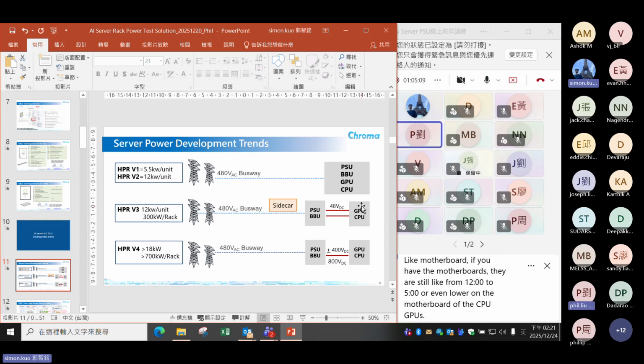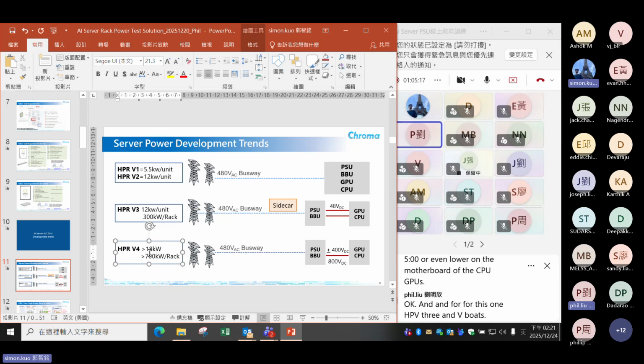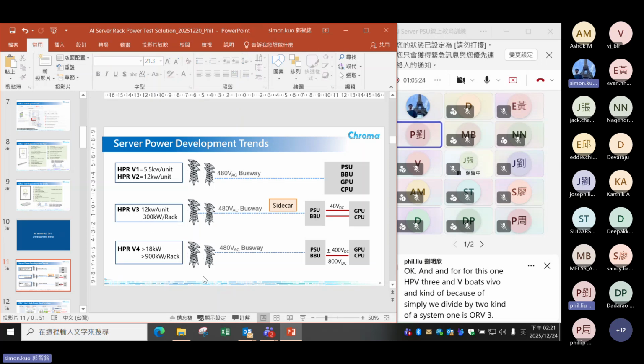Okay, and for this one, ORV3 and HVDC, because simply we divide into two kinds of system. One is ORV3, one is HVDC. So whether these three structures are dedicated for ORV3 or HVDC, because if you see down below, V4, V4, that's plus minus 400 volts and 800 volts. So it means I could define this as the HVDC structure, right? Yes, for the voltage above 48, we could call it HVDC at this moment.